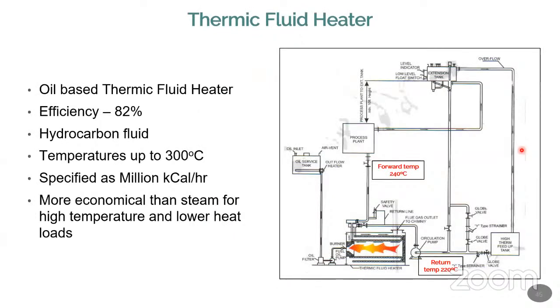The efficiency of the thermic fluid heater is basically 82%, and sometimes slightly more, but we need a separate oil system for this. So instead of using the boiler this is somewhat economical, but the initial cost is very high. The thermic fluid heater, TFH, is now coming in a bigger way to replace the boiler, especially for medium and low pressure applications. The operating temperature is even up to 300 degrees, and it is mainly used for process applications up to 300 degrees.